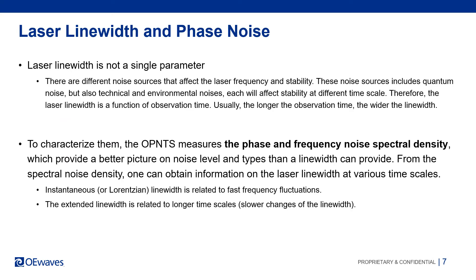Let's recap the last few slides, since this pertains to important issues related with laser noise characterization. Laser line width is not a single parameter, simply since there are many noise sources, each with its own time scales. Therefore, it is impossible to describe laser noise using one line width. Noise spectral density, on the other hand, can provide much more information within a single measurement. The OE 4000 directly measures the noise power spectral density, and provides a better picture of the noise sources inside and out of the laser.